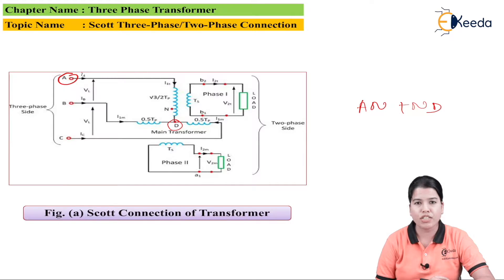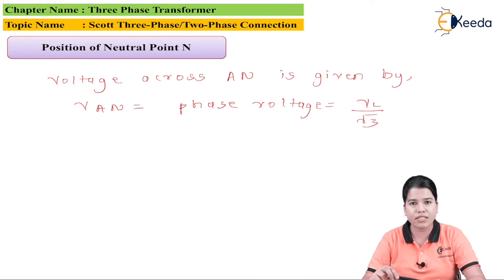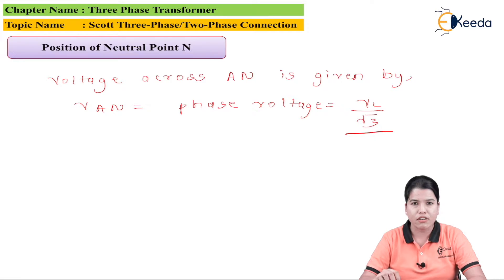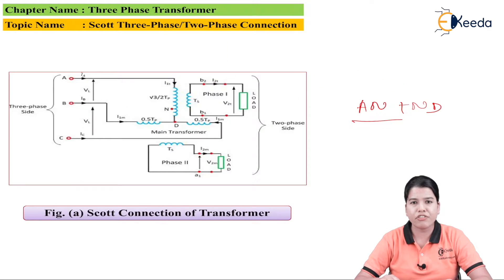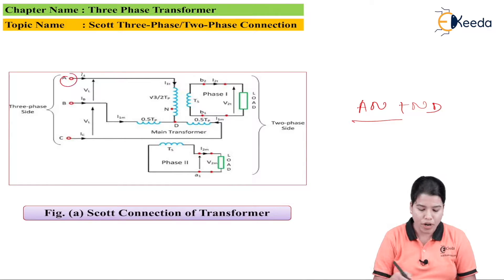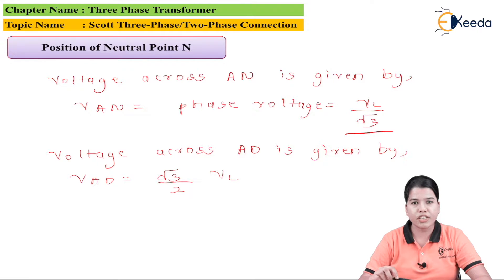First, let us find out the voltage across AN. The voltage across the point AN is nothing but the phase voltage. As this is a 3-phase 4-wire system with the neutral connected, this voltage will be VL divided by root 3. Now if we consider the point AD, that is the total primary winding of the teaser transformer, then the voltage across AD can be written as: VAD is equal to root 3 by 2 times VL. This formula we have already derived.